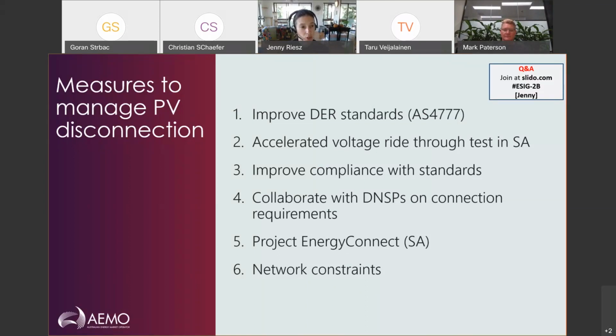We're also accelerating the introduction of particularly the voltage ride-through component, which is particularly what we're talking about here in South Australia, where we know that that's a particularly urgent issue. We're also working to improve compliance with those standards, because from other evidence, we've seen that around 30 to 40% of inverters look like they're not behaving in a way that's consistent with the standards. So we need to address that as well as improve the standards themselves. And we're working with distributors on their connection requirements as well to make sure that when they're adding additional protection systems, they also ride through these disturbances and aren't interfering with those ride-through requirements.